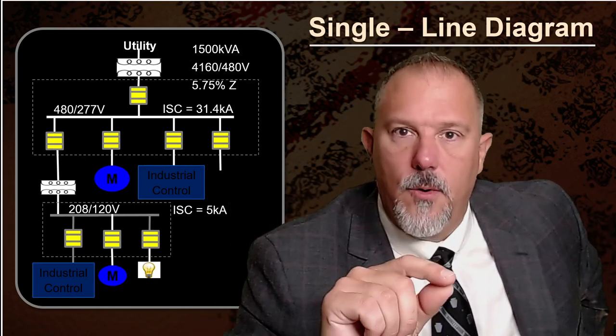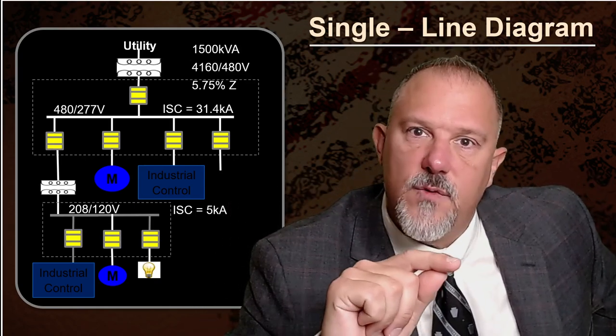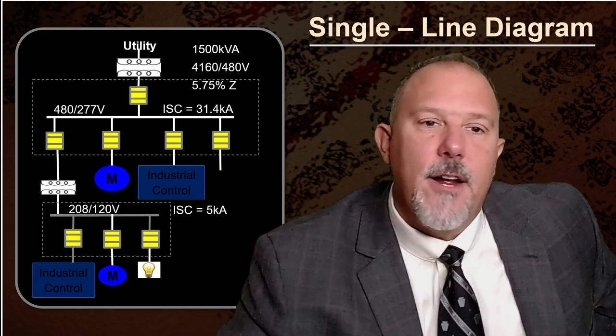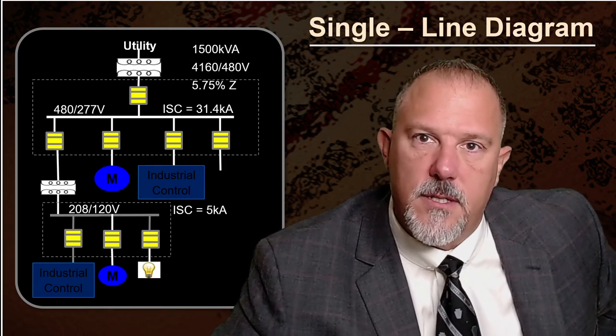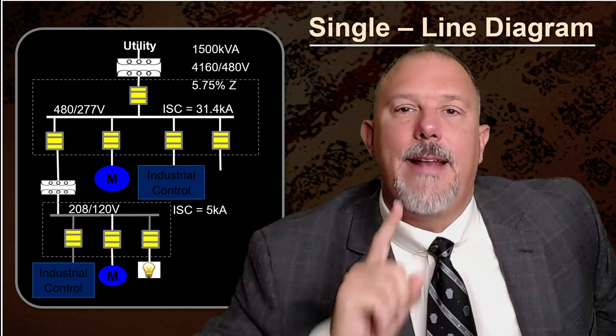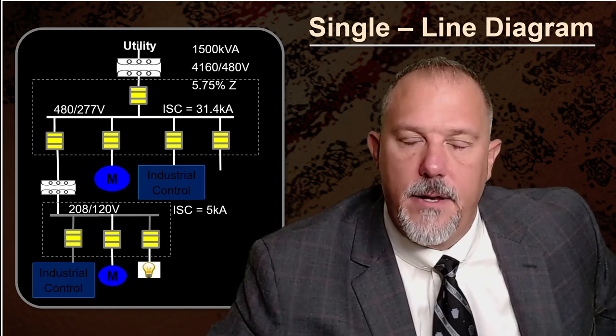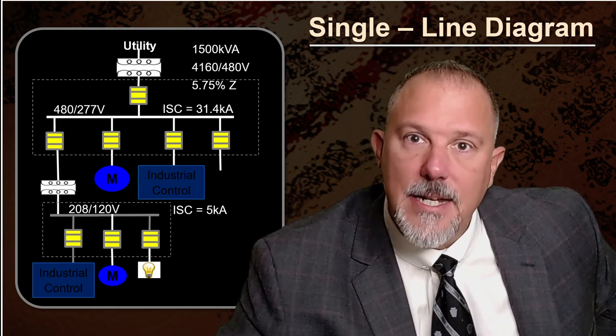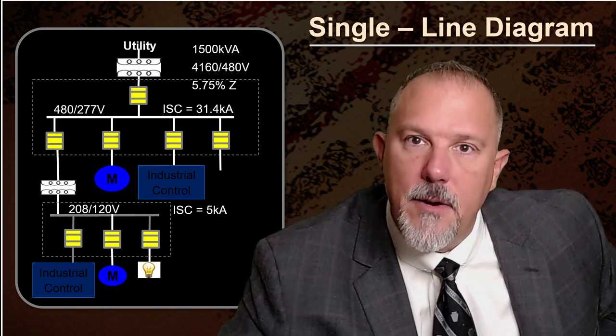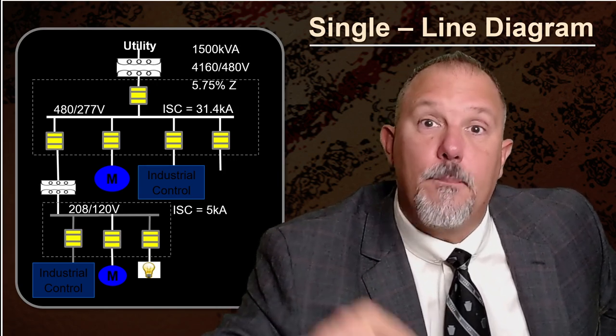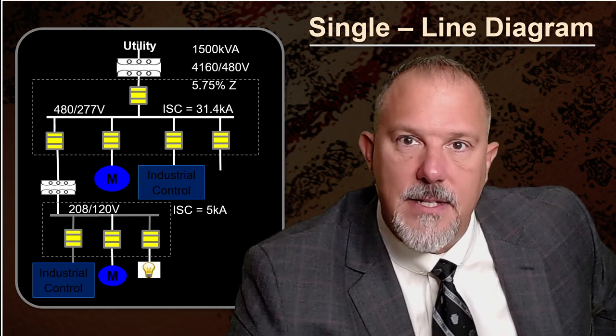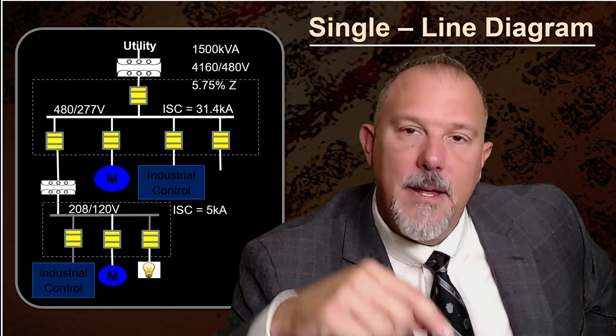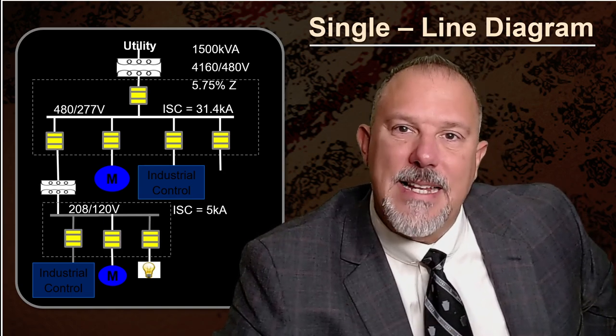How would I know the incident energy on the secondary of that transformer is much higher than any place else in my power distribution system? I know it without even doing an analysis. How do I know that? Because my protecting overcurrent protective device is on the primary of that transformer. And when I pick that protecting overcurrent protective device, I am artificially inflating its size.